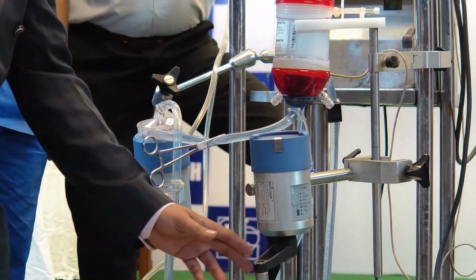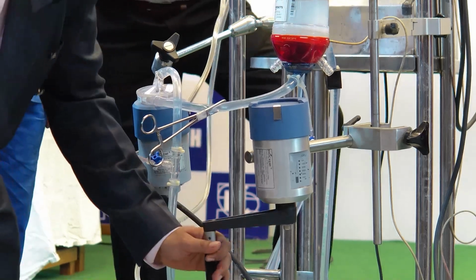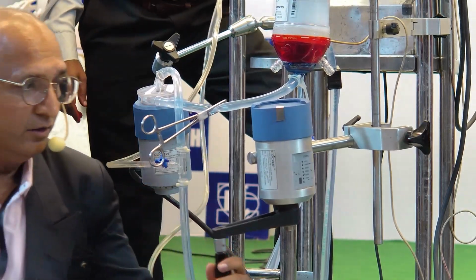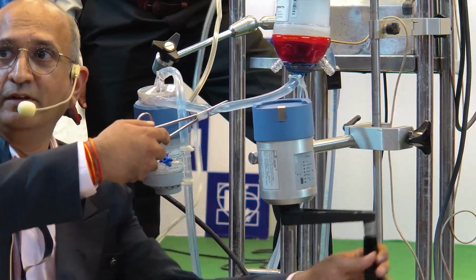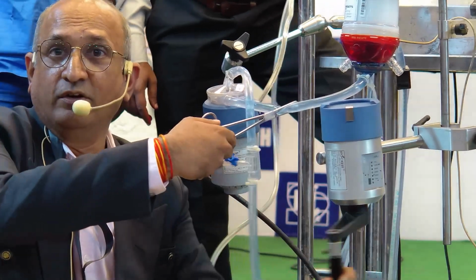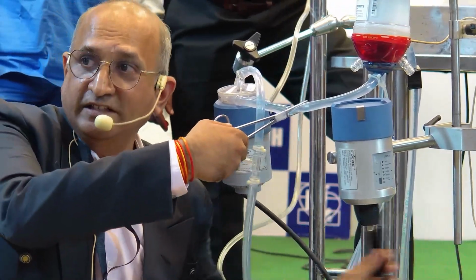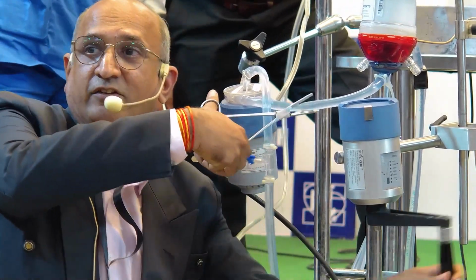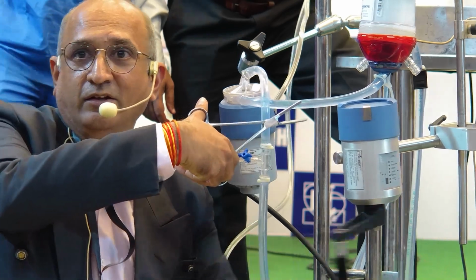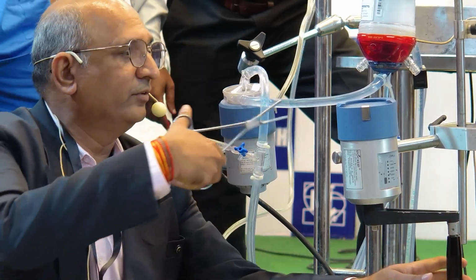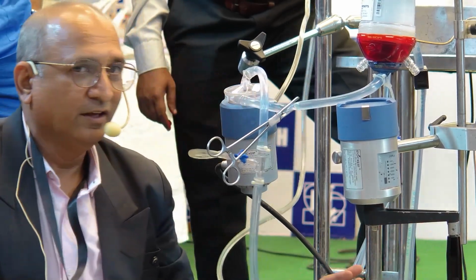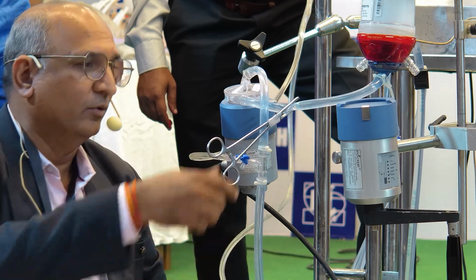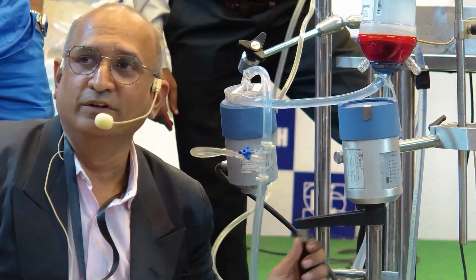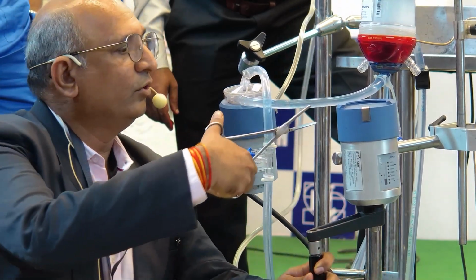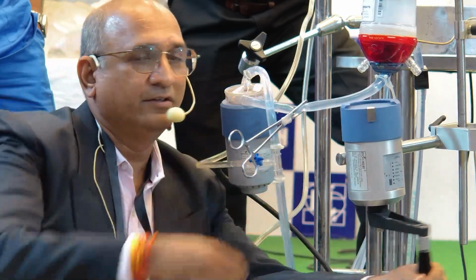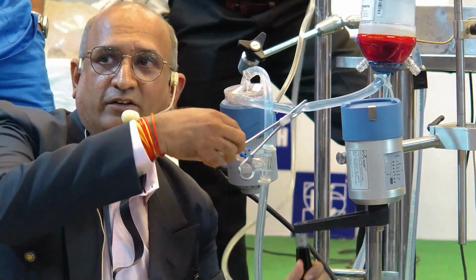You have to use both of your hands, you can't do it with one hand. You have to initiate flow to 1500, because when you initiate ECMO, we first increase the flow and then we release the clamp. You can't release the clamp first. So what happens most of the time, tomorrow what we are going to do I am going to tell you: you are going to release the clamp and then start moving this. No, that is not the right way. You have to start moving this and then you have to release the clamp.